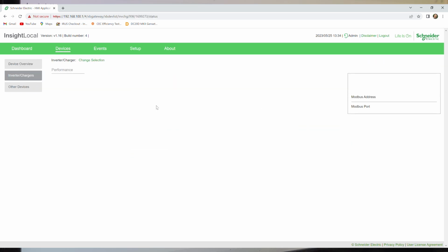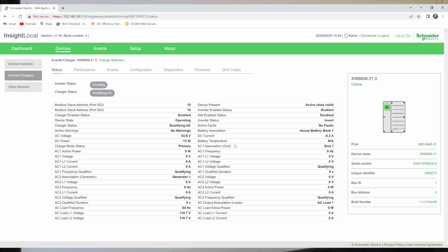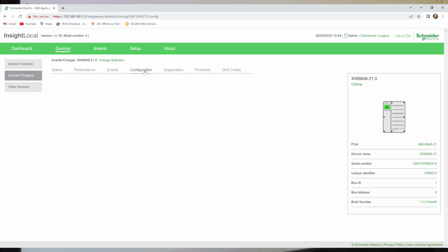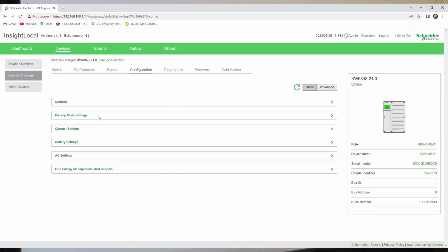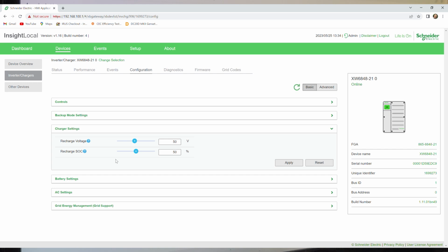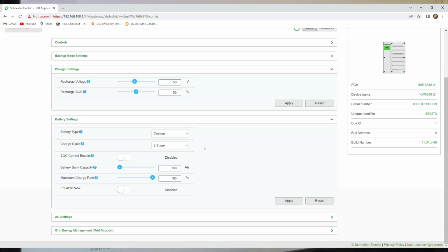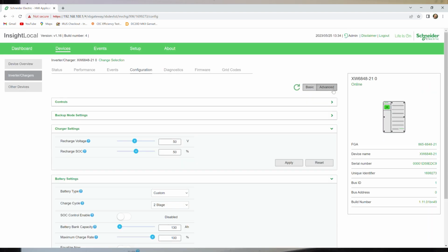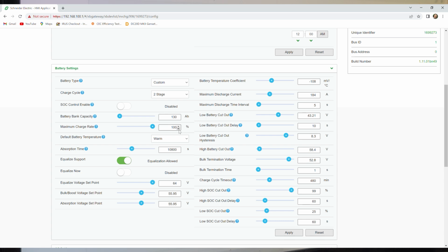Let's see what our maximum charge discharge ratings are. Configuration, charger settings. This is already set to 130 amp hours, that's what the battery is. Go advanced—maximum charge rate is 100%, this could be adjusted down. Bulk voltage is set to 55.95, absorption 55.95. Maximum discharge current is 184 amps for 5 seconds.